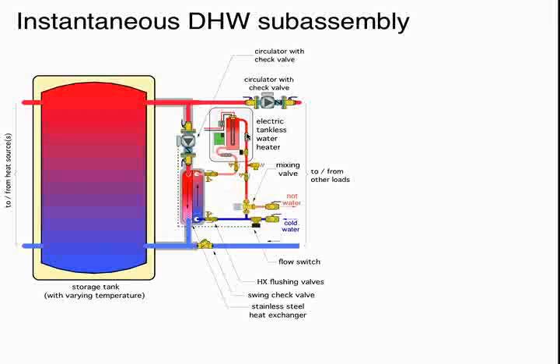Well, it depends on the temperature of this tank. If this tank was 170 degrees at the top, this might be 160 degree water coming out here. Now, it does show flowing through the electric auxiliary heater, but the thermostatic controls in that would be set, let's say, at 120 degrees. The elements will not fire. The water will pass through it, but we're not going to turn on any electrical flow to those elements. So it's just a pass-through.